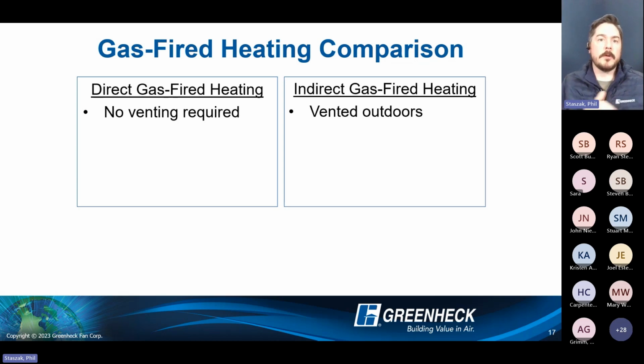People forget that it's 100% outside air coming across that open flame burner. So technically it's 100% thermal efficiency, because you're taking 0 degree entering air and throwing it across an open flame burner. All of the heat associated with burning LP or natural gas goes directly into the airstream. The concerns are what we'll talk about as far as the other things introduced into that airstream, but technically every single available BTU is where you want it, directly into the airstream to come into a space and get exhausted right back outside.